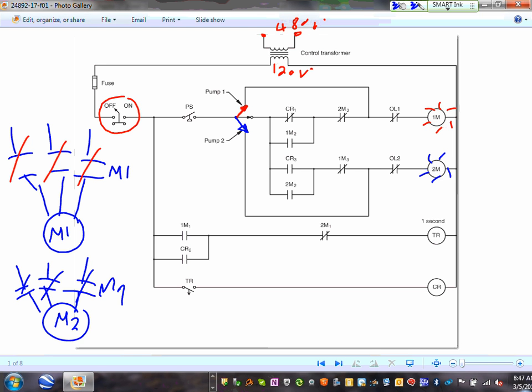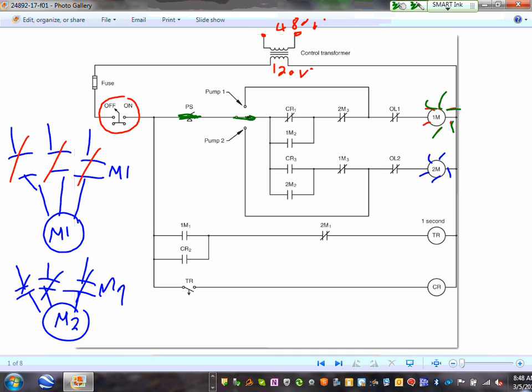If you select auto, the floating switch closes when the lift station — a well — fills with sludge. The water keeps rising until it hits the floating switch. When it hits, the floating switch closes the contacts. In auto, this will energize, these will close, and pump 1 starts working. At the same time, a contact closes to energize the timer. The timer starts timing.